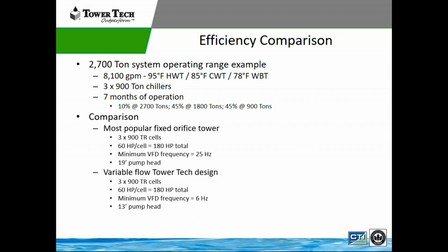So we're going to do a comparison. The most popular fixed orifice cooling tower, 3 900 ton cells. They have 60 horsepower per cell with a total horsepower of 180. Their minimum frequency, because they have a gearbox, is 25 hertz, and they have 19 feet of head on that cooling tower. Versus the TowerTech solution, which is 3 900 ton cells. We're running 60 horsepower per cell with 180 total horsepower, and then a minimum VFD frequency of 6 hertz with 13 feet of head. Now, on paper, when we looked at this traditionally, we would just look at the total horsepower of a cooling tower and say they're very similar because they're both at 180 horsepower total on a cooling tower system.